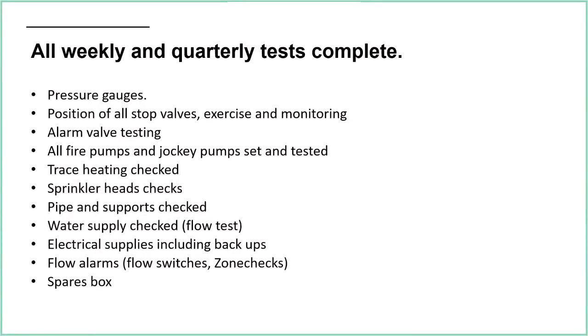Water supply checked, so we actually do a flow test, or that might involve firing the fire pump up, doing that kind of test return and checking the actual flow. So we're actually checking the fire pump. On each fire pump there ought to be a plaque, a metal disc, which tells you the manufacturer, the manufacturing number, the date of manufacture, things like that. But also, very importantly, what duty that pump is designed to. And then you can actually do some testing. You can plot some points on a curve, and you can verify that the pump is actually doing what it's supposed to be doing.